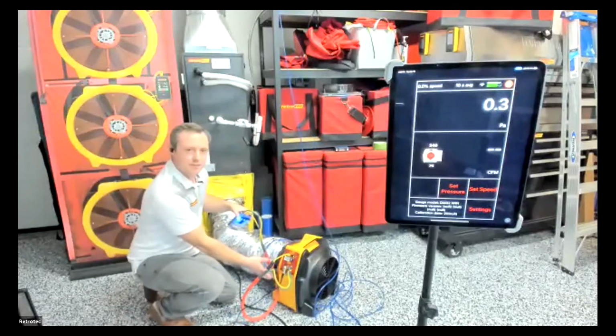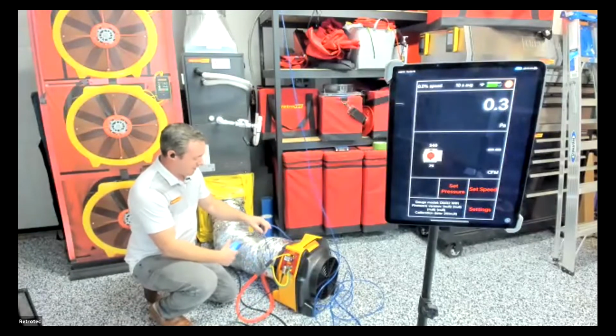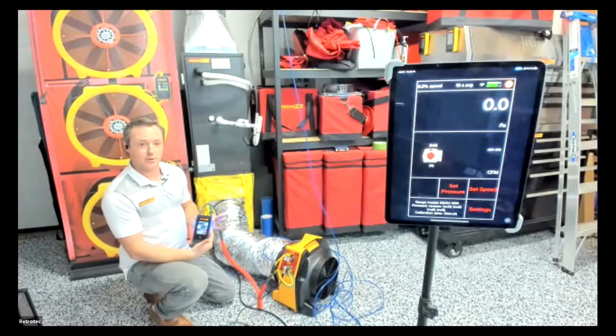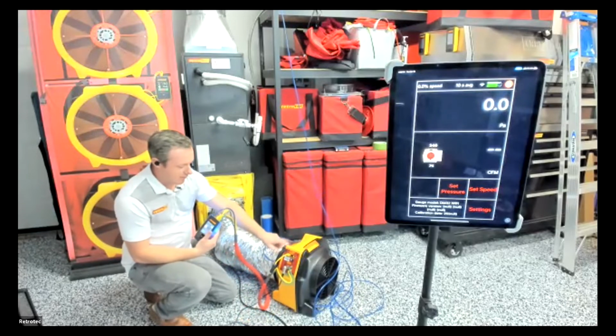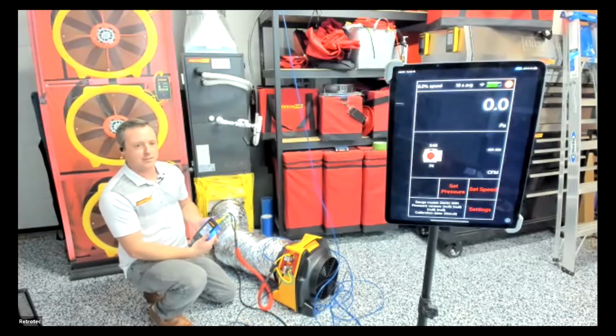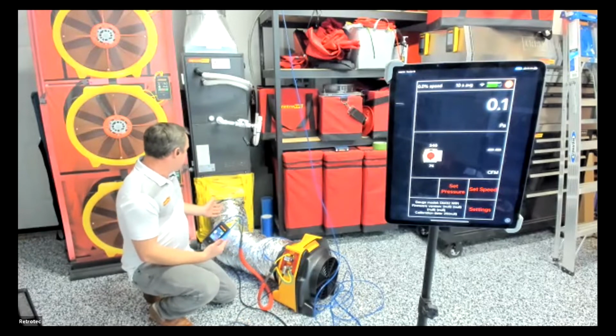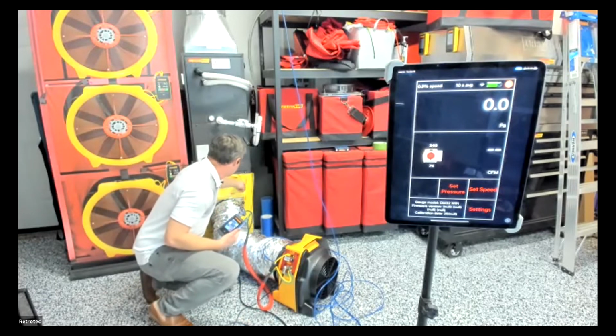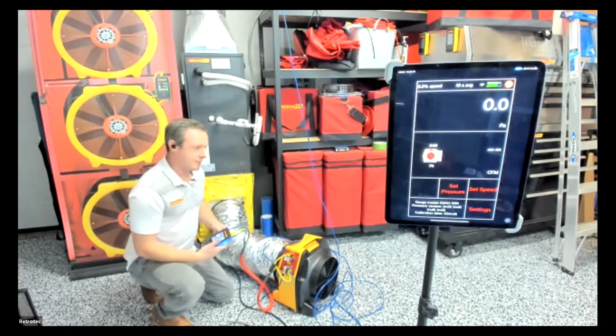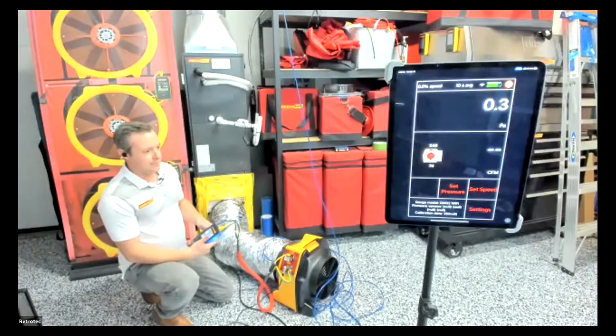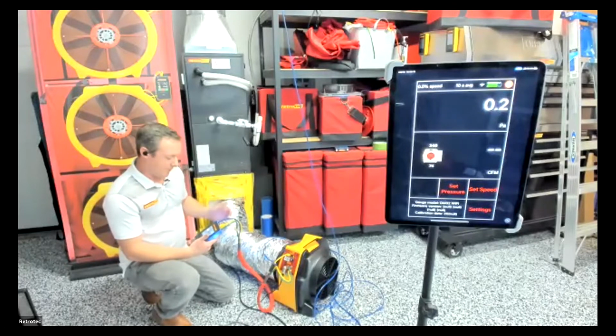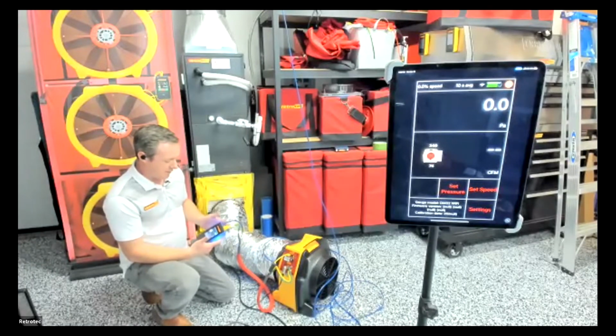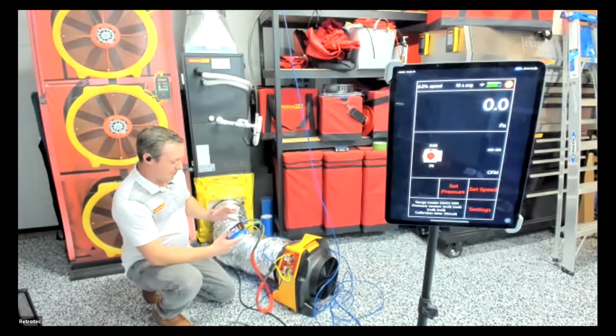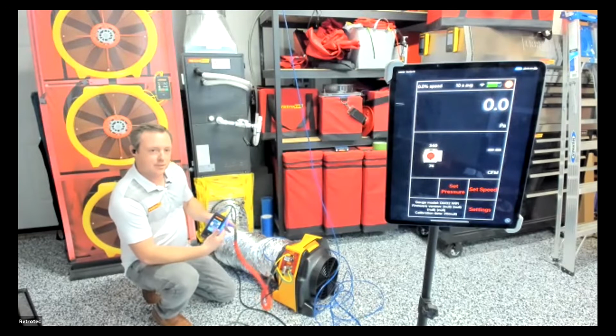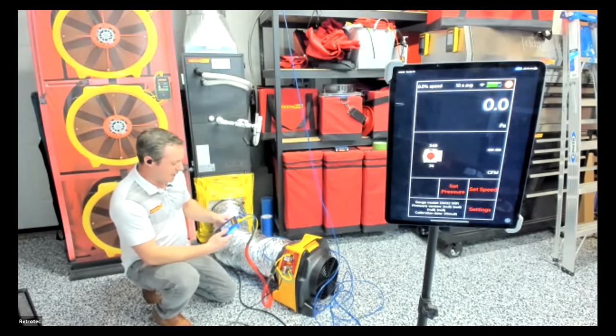So there's a couple of ways that you can do this. Like I mentioned before, the gauge can be the control. There's a manual dial here on the fan, but if I'm doing a total duct leakage test where I'm testing the whole system, I'm just going to let the gauge do the work for me. So there's a few things that I want to make sure I have set up correctly in the gauge. There's different outputs that we can have. So if you're not familiar with the DM32 gauge, let me run through this right quick.